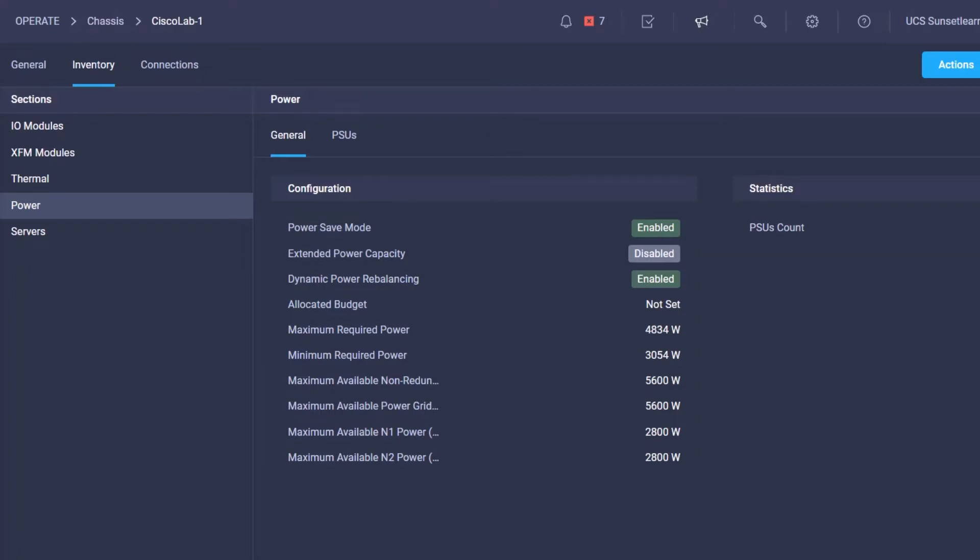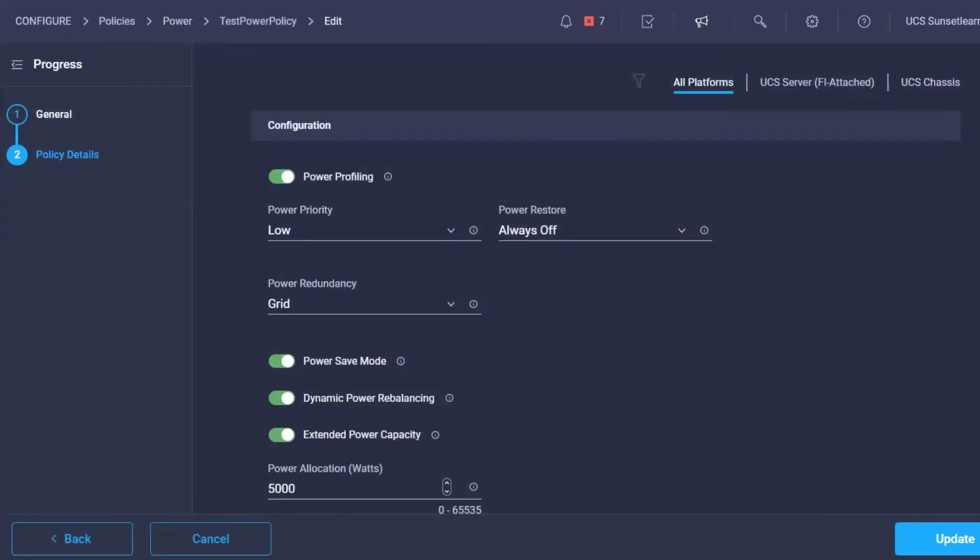To set the maximum power budget we will need to create a power policy. By setting the power budget or power allocation down here at the bottom to 5000, this ensures that the server will not oversubscribe the chassis power which could cause an outage.